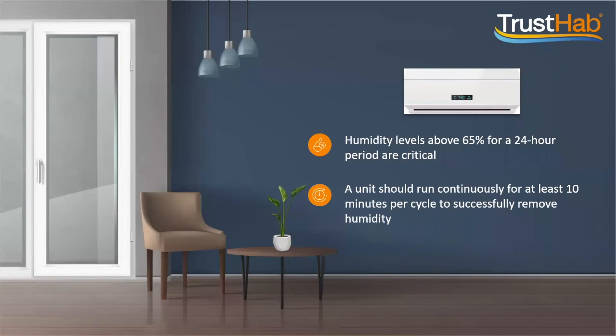So something else worth noting, humidity levels are often considered another very important metric when it comes to spotting risky conditions within a residence. For tenants that pay their own utility bills, it's common for them to turn off the HVAC unit altogether in an attempt to save some money, not realizing how this can rapidly create an environment that is favorable for mold growth. For maintenance staff, it's important to know that humidity levels above 65% for a 24-hour period are critical. And to successfully remove humidity from a space and avoid damage to equipment, a unit should run continuously for at least 10 minutes per cycle.